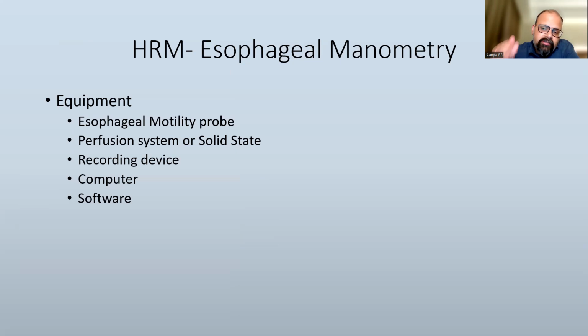So what is the equipment that is actually needed? What are the various parts of the equipment? You have the catheter or the probe itself. You have a perfusion system if you're using water perfused equipment, or you have a solid state processor if you're using solid state equipment. You will need a recording device which ultimately records the whole reading, and of course you will need software and a computer to interpret it. So those are the equipment that you need. Now, perfusion systems are of various types. Different manufacturers use different perfusion systems, and that is a problem, and in a way a good thing also.